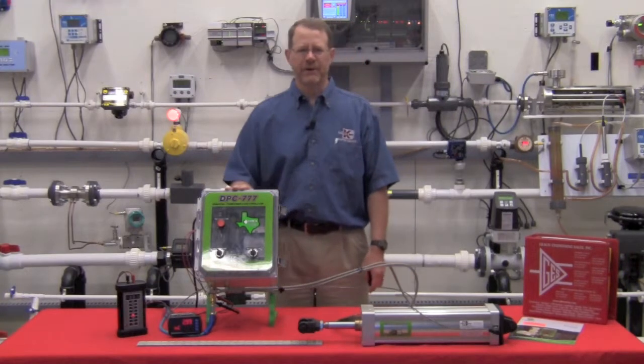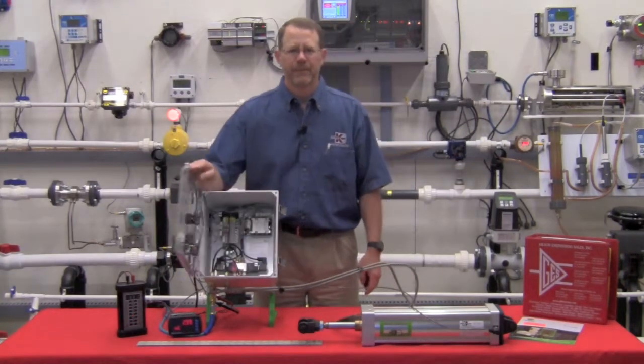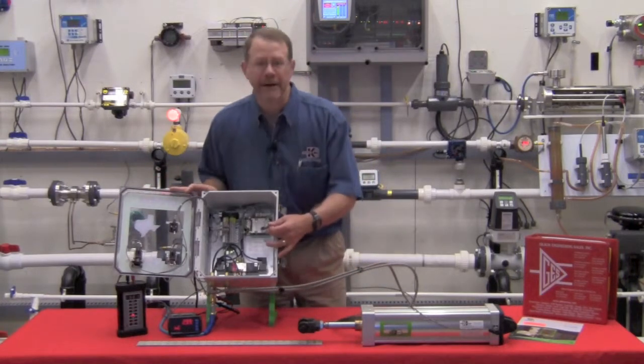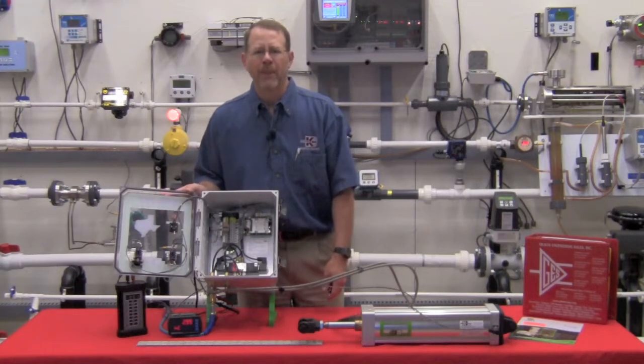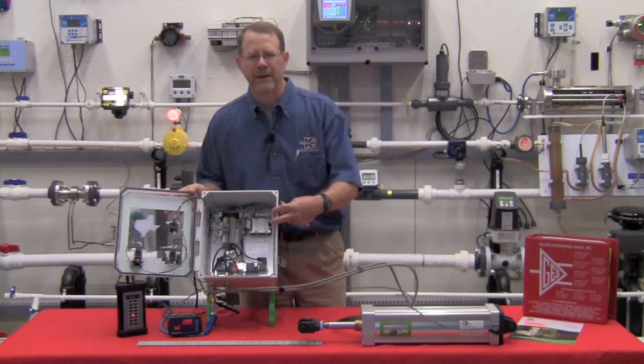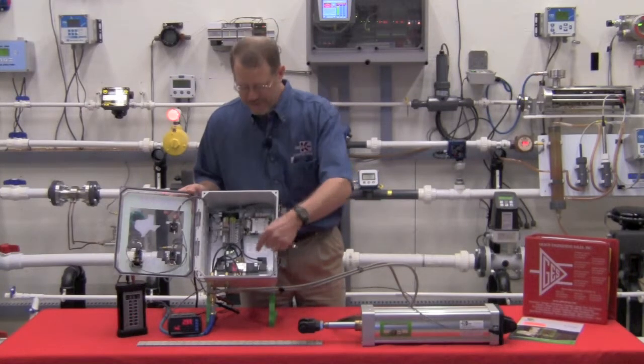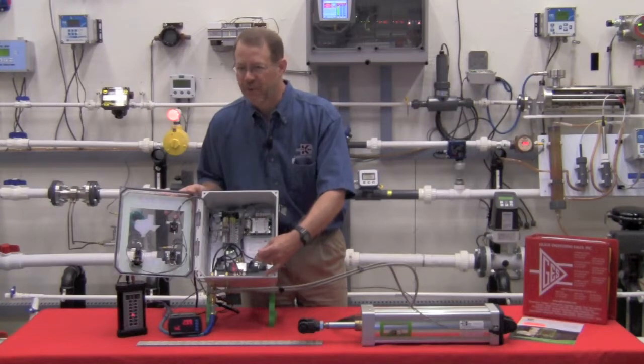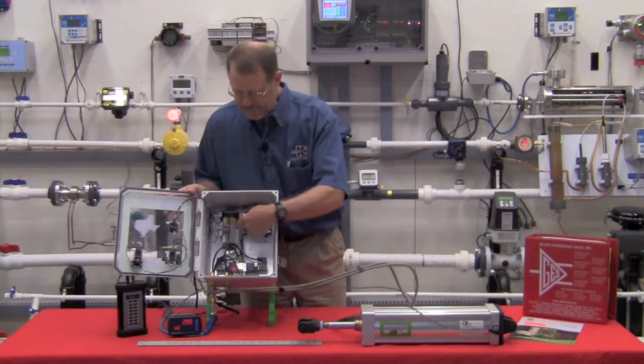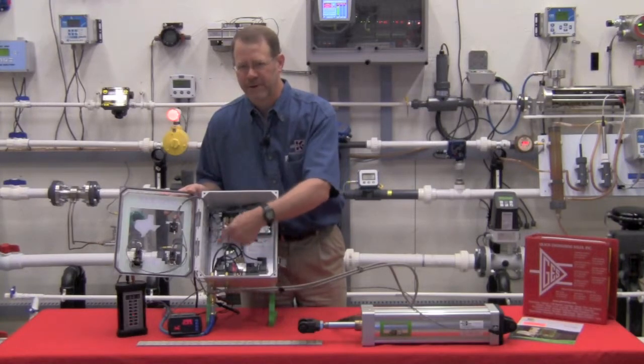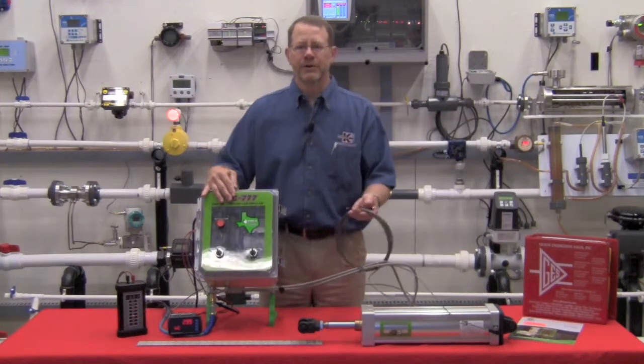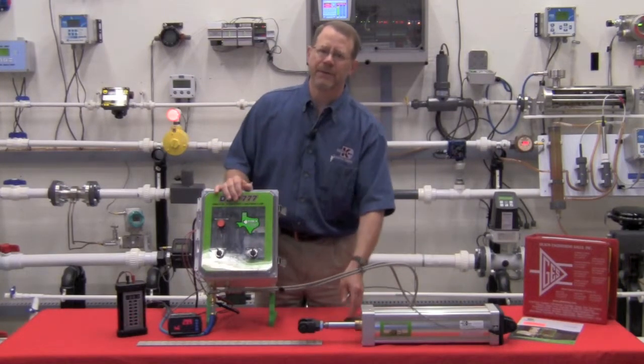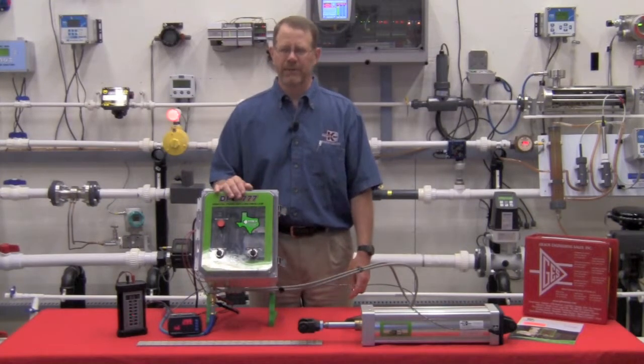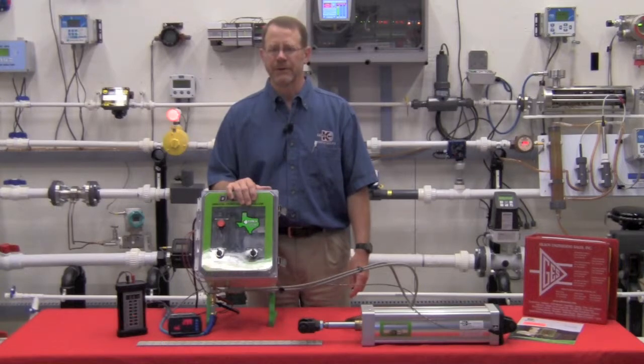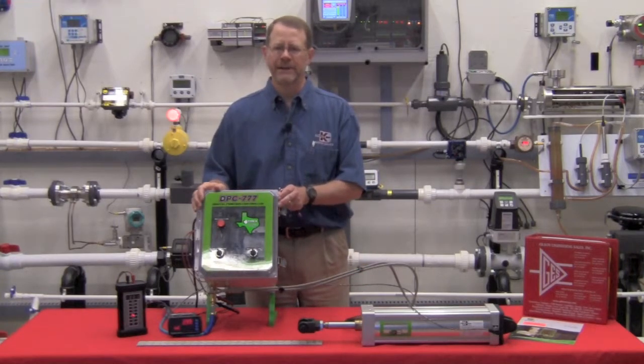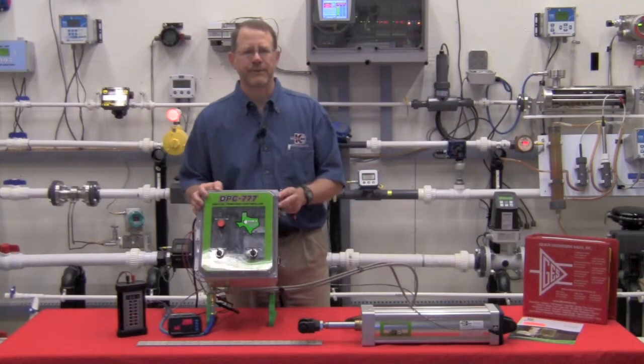The DPC777 controller consists of 5 principal components. The digital control module, or the DCM, located right here, is the main component of the DPC. All operations are performed on the DCM by manipulating the 3 push buttons. No additional calibration equipment is needed. The digital pneumatic interface module, which is a 4-way, 3-position proportional valve. Then there's assorted switches on the terminal strip, bulkhead fittings, and air connections. We also have shielded 3-wire conductor cable with a quick disconnect at the cylinder, and is available in 25-foot or 100-foot lengths. And finally, there's the NEMA 4X fiberglass enclosure that is rated to -20 to +100 degrees F.